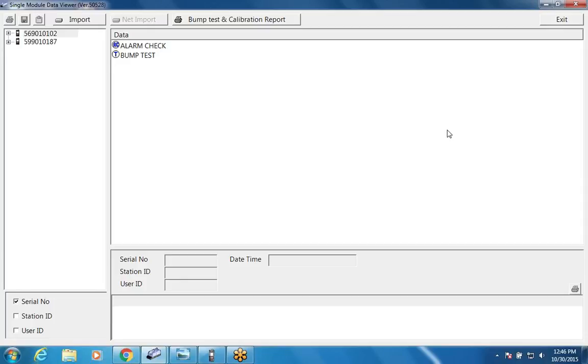And you can see that it comes up and it shows you what sensor combination you have in each unit. I've got a 5-gas unit in the main dock, and I've got a 4-gas unit in the second dock. And it gives you the ability to turn the unit off. There's a button that says Detector off, so I could actually turn the instrument off using that button. I can make it active or inactive if I don't want to calibrate that particular unit or download the data. I can make it inactive if I want to just bypass it when I do a calibration. So I'm going to go back to the function screen.